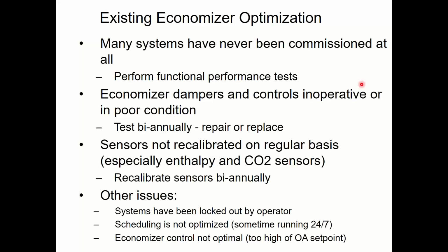Isn't that pretty sweet? I'm putting in all these occupancy sensors for the lights and stuff. And I went and saw that I was sucking all that cold air in the winter. I screwed that thing shut. Now we don't have to pay to heat it. I was like, yeah, but you're also not ventilating your building. He's like, oh, that's not good. I'm like, and you're not getting all the free cooling on the economizer, and your compressor's got to run a lot more. He's like, holy crap, dude, that's going to hurt my bonus. Like, this is the mentality of some of the people that are doing it. They don't know what they're doing, so they just do it.